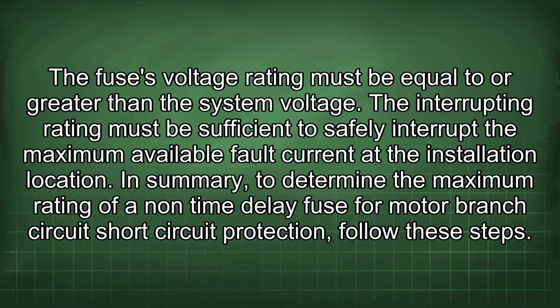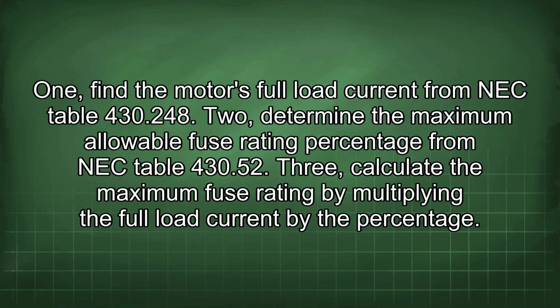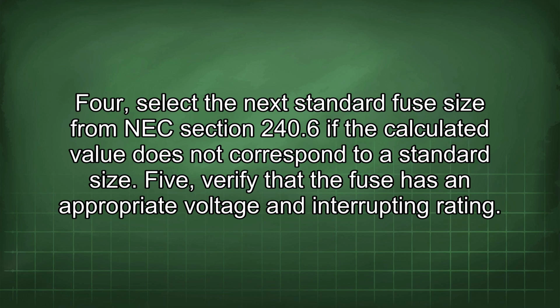In summary, to determine the maximum rating of a non-time delay fuse for motor branch circuit short circuit protection, follow these steps. 1. Find the motor's full load current from NEC Table 430.248. 2. Determine the maximum allowable fuse rating percentage from NEC Table 430.52. 3. Calculate the maximum fuse rating by multiplying the full load current by the percentage. 4. Select the next standard fuse size from NEC section 240.6 if the calculated value does not correspond to a standard size. 5. Verify that the fuse has an appropriate voltage and interrupting rating.